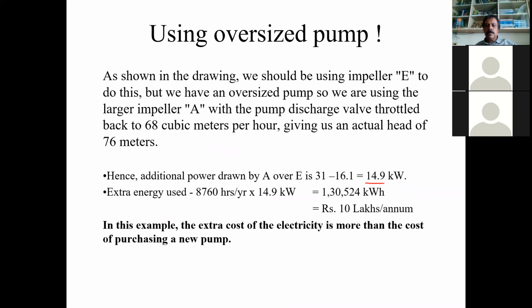The difference in power consumption is 14.9 kilowatt, and if you're operating for 1 year, this is the amount of additional energy that you're going to lose. In terms of money, it is about 10 lakhs per annum. 10 lakhs per annum, and then you calculate for 20 years how much money you're going to lose. That's about 200 lakhs, which is about 2 crores. In a 20-year lifespan of the pump, what you'll be losing is 2 crores.